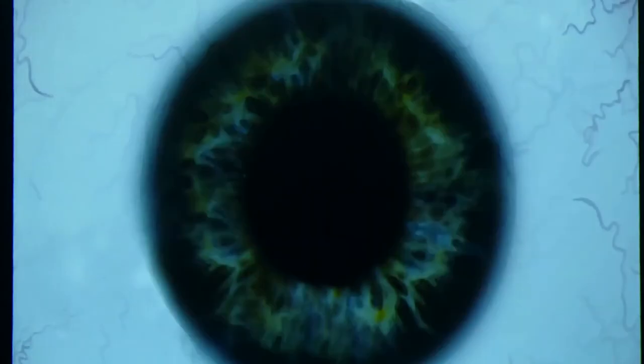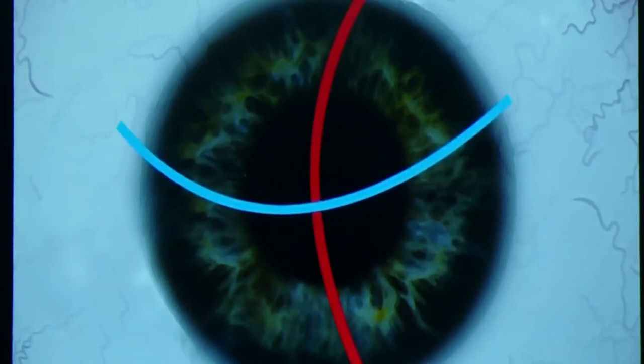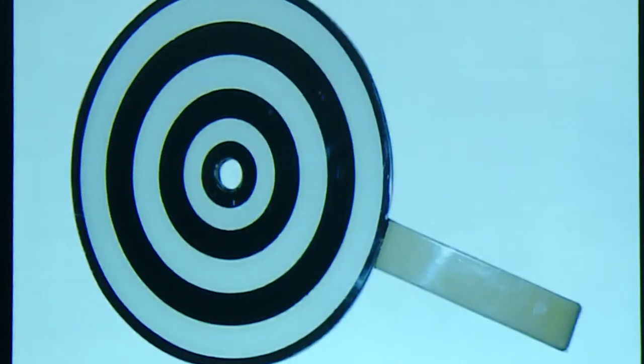All topographers were initially designed to generate keratometry — the steep and flat keratometry in vertical, horizontal, or oblique meridians. Looking at the earliest Placido-based devices, if you look carefully, there is a central hole in the Placido disc which is used as an aperture to view the cornea. This means the central 2 to 2.5 mm of the cornea is actually not measured in a purely Placido-based system — which is one disadvantage.